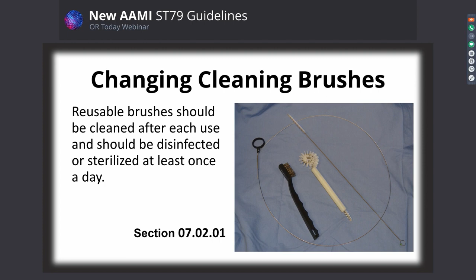Changing cleaning brushes: reusable brushes should be cleaned after each use, and disinfected or sterilized at least once a day. Very important, since sometimes people are short on time and inventory and use brushes with bristles falling off over and over again. But this is now indicated in the newest ST79 releases.